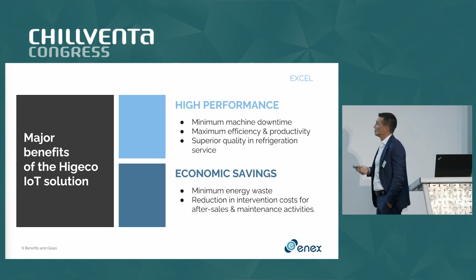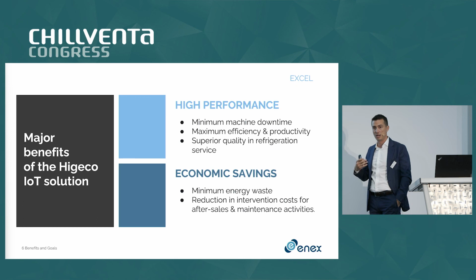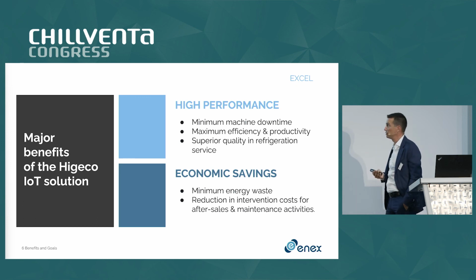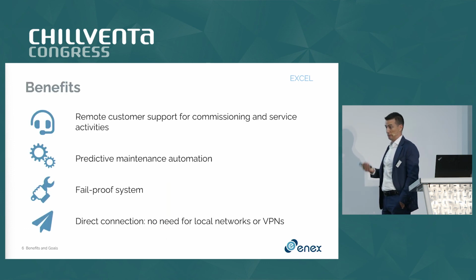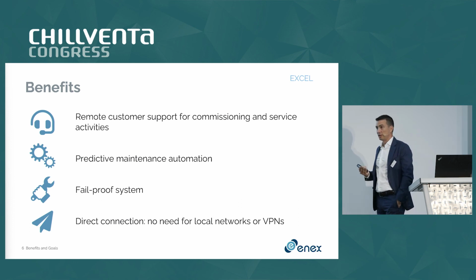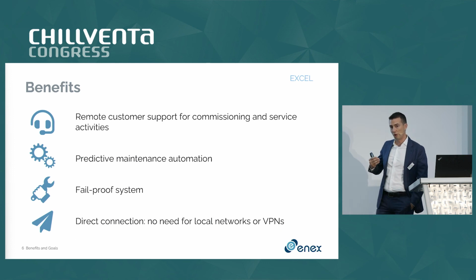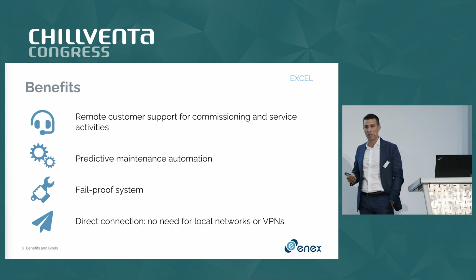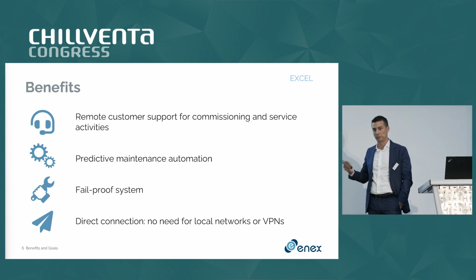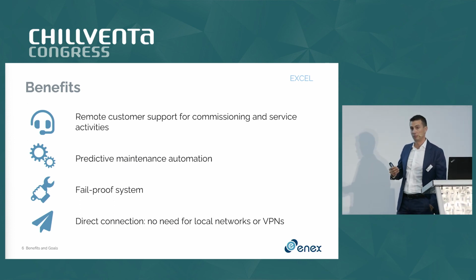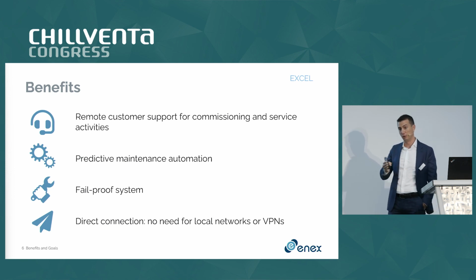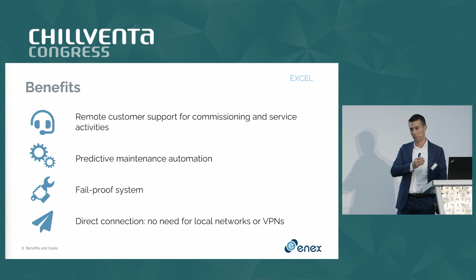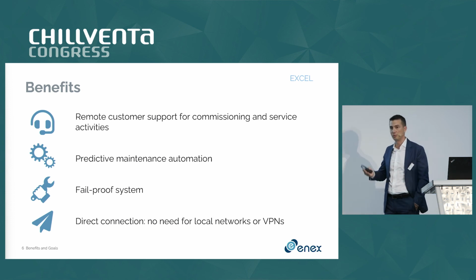Other benefits, of course: we have remote customer support for commissioning and service, which we are able to provide by having an enhanced and comprehensive platform which we can connect to. We are developing highly performing predictive maintenance automation algorithms. These algorithms are very important because by the use of other sensors, other controls which can be installed on the unit and connected to our data logger, we could predict in time when it's time to change the oil. So this will remove the obligation of changing the oil every 6 months, for example.